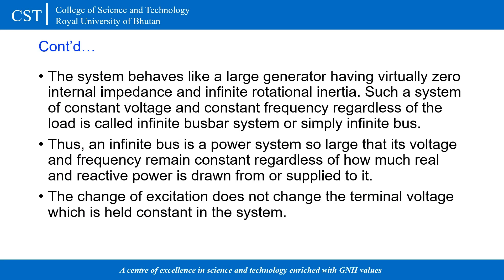In this infinite bus system, there is zero internal impedance because generators are connected in parallel. In parallel connection, the internal impedance tends to minimum or zero, and the rotational inertia is infinite. When there is zero internal impedance and infinite rotational energy, the system becomes constant in both voltage and frequency, regardless of load being connected or disconnected from the infinite bus.